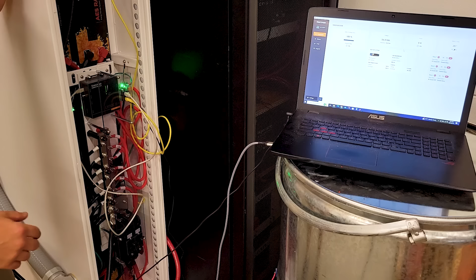After that test, I reached out to Discover Battery and was told that the cabinet was UL tested to thermal limits with 500 amps continuous, and it passed all those UL testings, but it was done with the conductors directly to the bus bars without the circuit breakers in place. Now the circuit breakers are made by a third party, that's Carling Tech, and they are also UL listed circuit breakers. It would be cool if we could get up there, and I'd like to know if I just have a bad circuit breaker or not. So I'd like to test the circuit breakers independently.